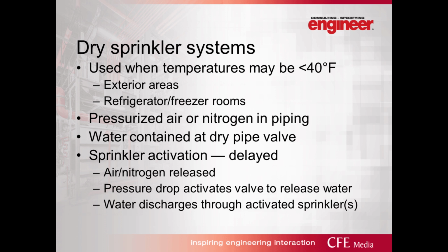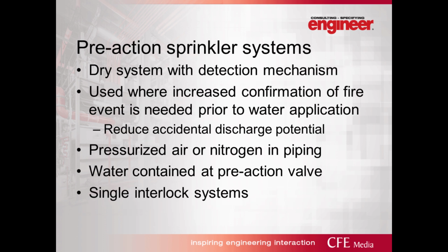Once the sprinkler activates in a dry system, the air or nitrogen is dropped out where that sprinkler activates. The pressure drops and activates the valve. Water is released from the valve and flows through the piping and discharges through whichever sprinklers are activated. Again, similar to the wet system, only activated sprinklers will discharge water. It's not intended to be a system that discharges all water through all sprinklers at the same time. Given that the water is held back at the dry pipe valve instead of in the sprinkler piping overhead, suppression from a dry system is obviously delayed when compared to a wet system, so something to consider.